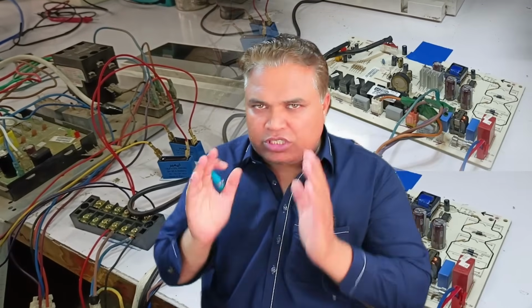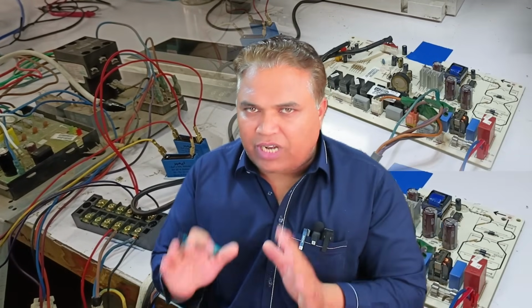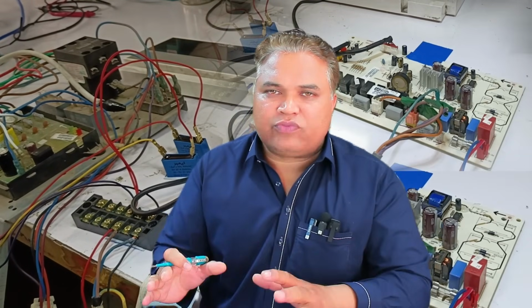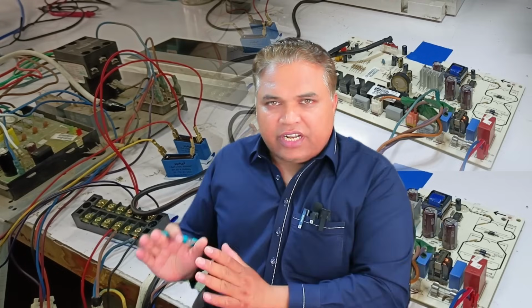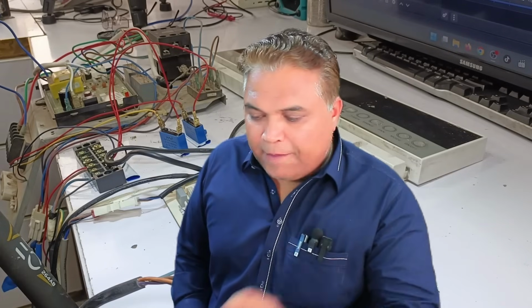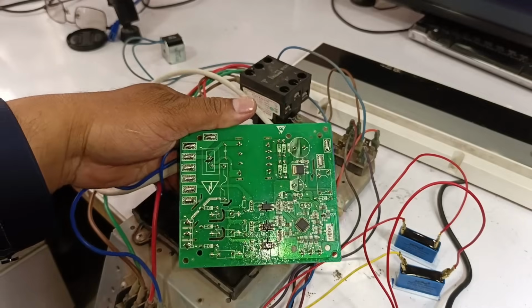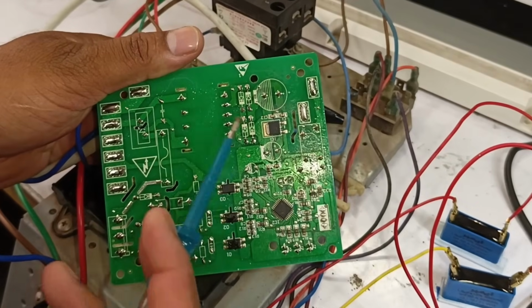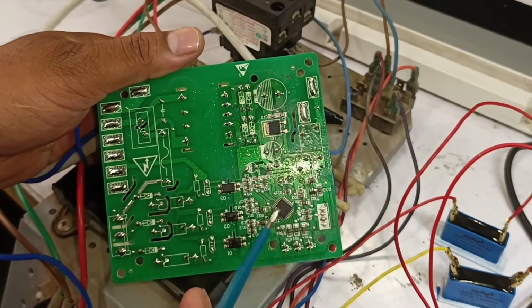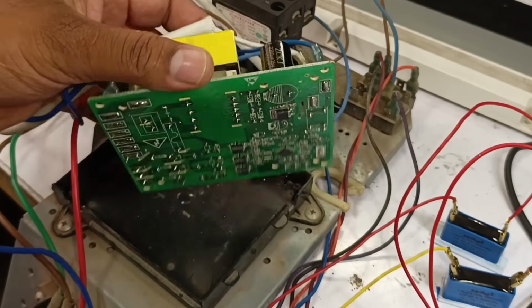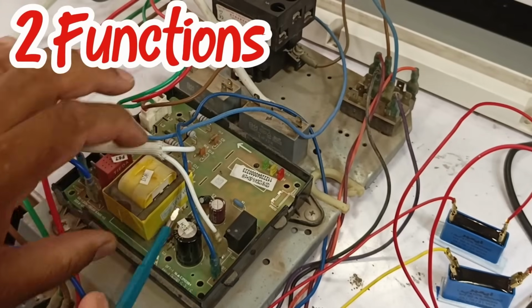Now, let me explain in detail why this signal is sent to the indoor board. The signal coming from the outdoor unit simply informs the indoor PCB that both of the control systems on the outdoor PCB are working properly. If those systems are functioning correctly, then the indoor unit will allow the outdoor unit to start and begin its operations. The outdoor circuit board includes a complete microcontroller system and several other components. However, the entire setup on this board is only controlling 2 functions.